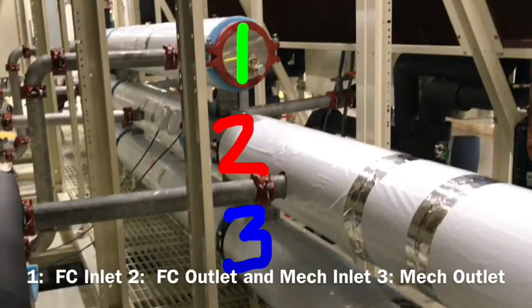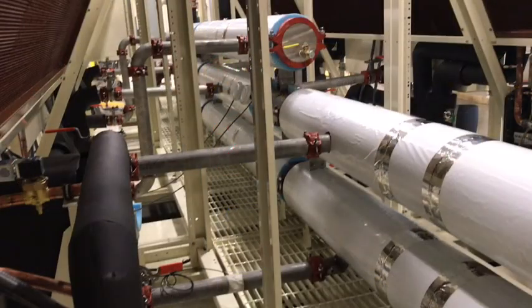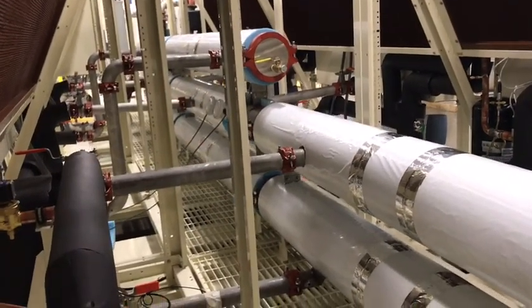The 3 headers are numbered here. Green number 1 is the free cool inlet. That's water coming into this array. Red number 2 is the free cool outlet, water coming out of the free cooling coils. It also serves as the inlet to the mechanical modules.